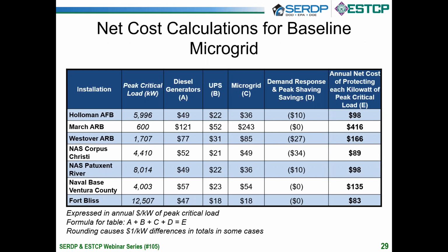As to the demand response and peak shaving savings, some installations like Corpus Christi have high peak demand charges on their utility bills and participation options for demand response. They can save quite a bit through operating this baseline microgrid for economic purposes. Savings of $34 per kilowatt annually pays for 70% of the microgrid all on its own. Other installations like Fort Bliss and the 2 California bases, March and Ventura County, have utility tariff or state policy barriers to running diesel generators for economic purposes, and therefore see zero savings in column D.